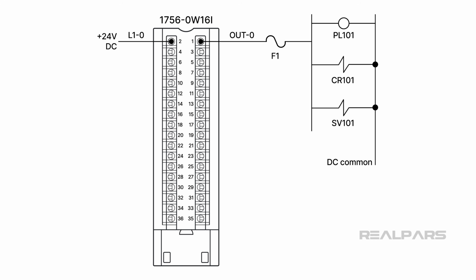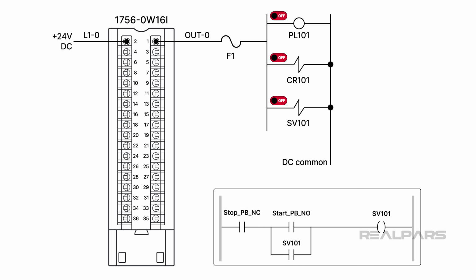Let's move on to a circuit with a short. A single dry relay digital output from a PLC drives 3 field devices wired in parallel. All 3 loads share the same 2-amp fused 24 volts DC supply. Our loads include a pilot lamp, a control relay, and a small solenoid valve. In our fault scenario, the pilot lamp is off, and the electromagnetic devices are de-energized. Everything appears to be operating correctly on the software side.